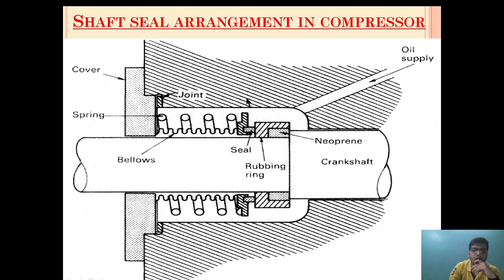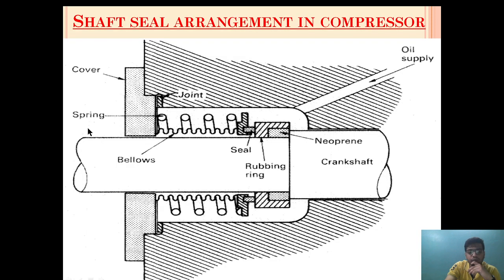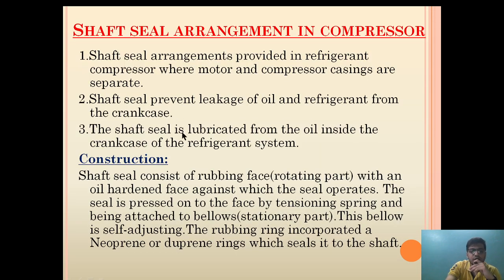The shaft seal prevents the leakage of oil and refrigerant from the crankcase. As you know, the refrigerant operates in a closed cycle, so any leakage outside the system will cause loss of refrigerant and will also reduce the effect of refrigeration. To ensure there is no loss in the cycle, we provide an enclosed shaft seal arrangement which will prevent the leakage.